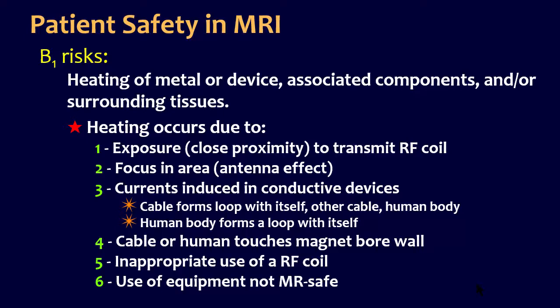With regards to B1 risk, this heating is very, very serious, and towards the end of this talk I'm going to hit more on that, because I think more injuries are occurring to patients because of this and fewer injuries due to B0. I just don't think that we put enough training, education, and accessories in place for technologists and radiographers to ensure that their patients are safe. I just think that the risk is huge, and there you can see the different items that result in these burns.